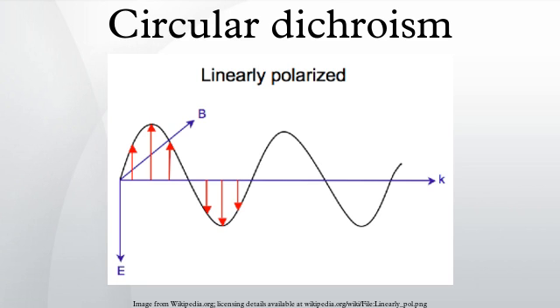The usual light source in these instruments is a high pressure, short arc xenon lamp. Ordinary xenon arc lamps are unsuitable for use in the low UV. Instead, specially constructed lamps with envelopes made from high purity synthetic fused silica must be used. Light from synchrotron sources has a much higher flux at short wavelengths and has been used to record CD down to 160 nanometers. Recently the CD spectrophotometer at the Electron Storage Ring Facility ISA at the University of Aarhus in Denmark was used to record solid state CD spectra down to 120 nanometers. At the quantum mechanical level, the information content of circular dichroism and optical rotation are identical.